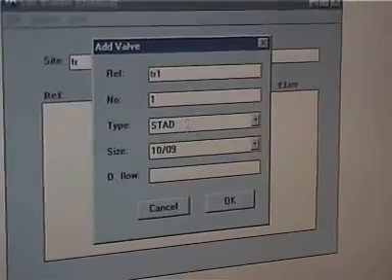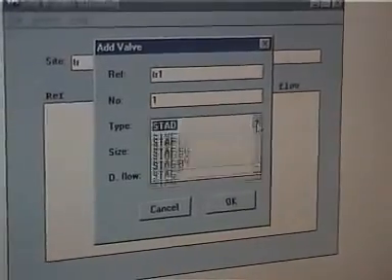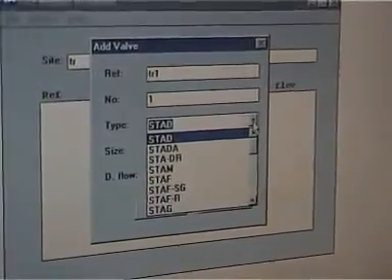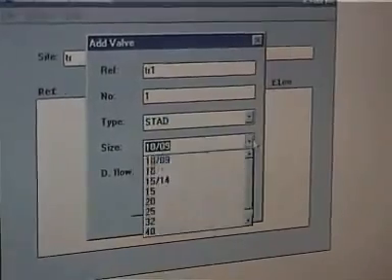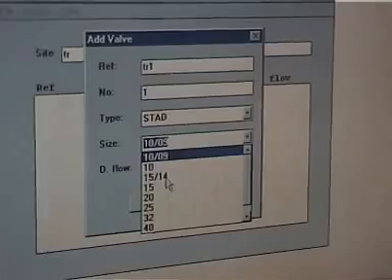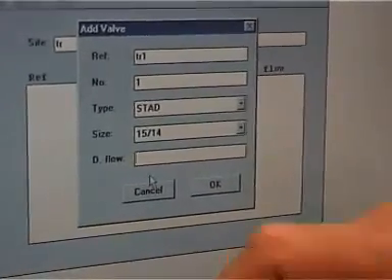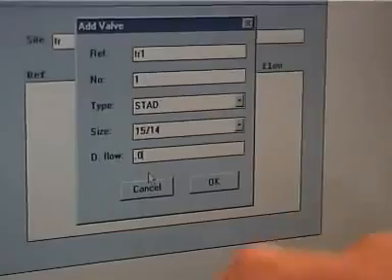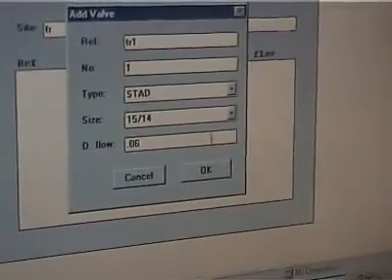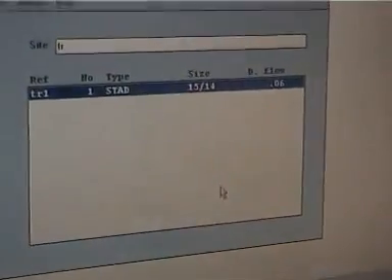We know the type of valve is a STAD. If we didn't and we needed to change the valve at that time, these are the other options we've got. The size of the valve on this installation is a 15-14, and then we type in our required flow rate. Once done that, we hit the OK button, puts it up on the screen.